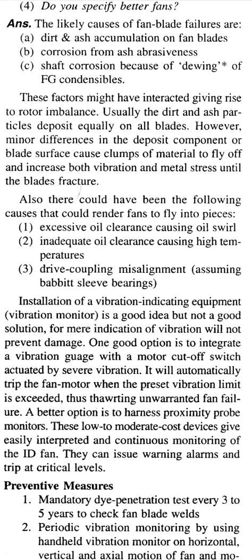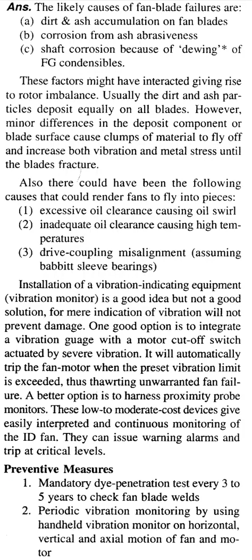Also, there could have been the following causes that could render fans to fly into pieces. 1. Excessive oil clearance causing oil swirl, inadequate oil clearance causing high temperatures, drive coupling misalignment, assuming Babbitt sleeve bearings. Installation of vibration indicating equipment, a vibration monitor, is a good idea, but not a good solution, for mere indication of vibration will not prevent damage.